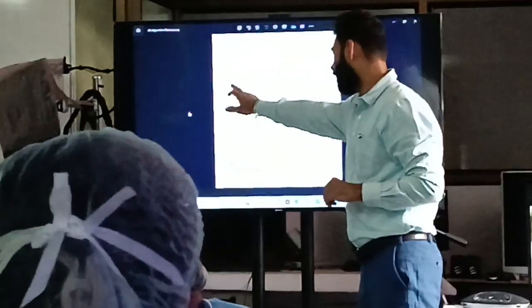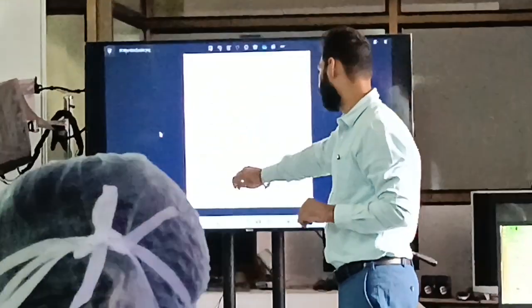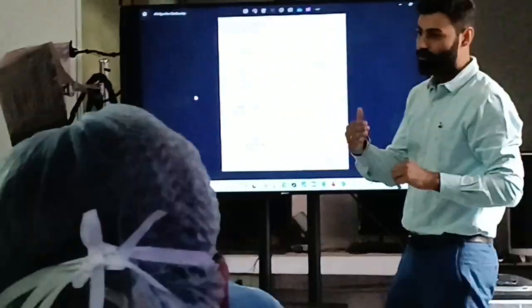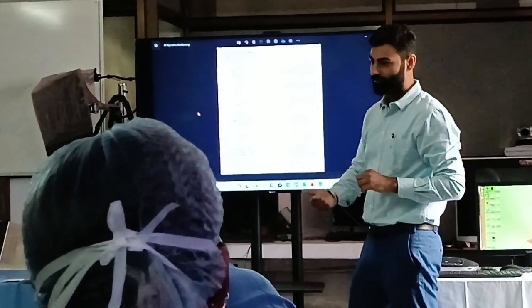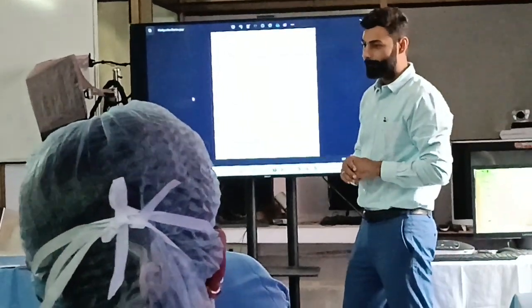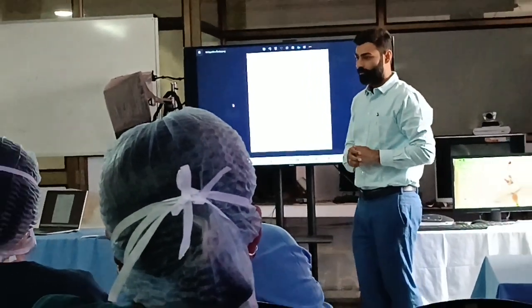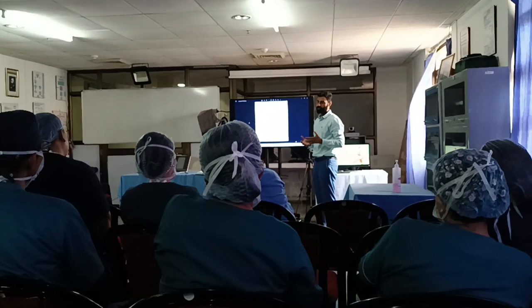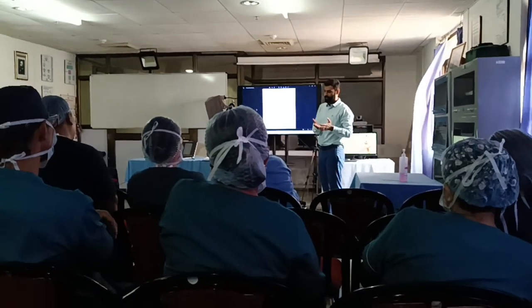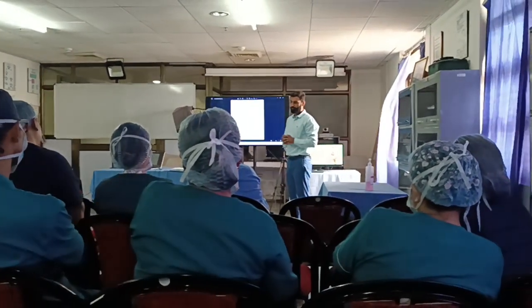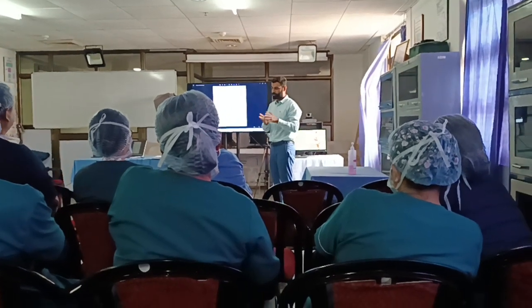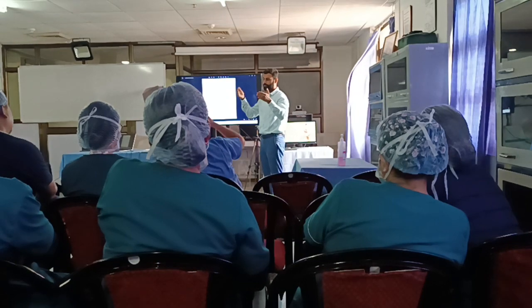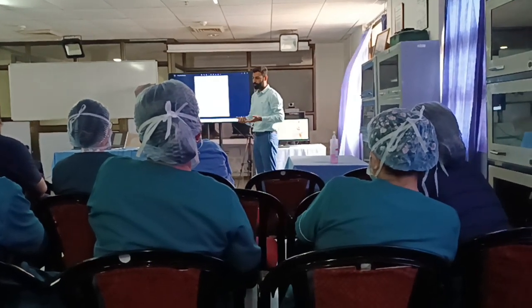If the CT of INTEM and HEPTEM ratio is more than 1.25, that means we have to transfuse with protamine. The moment you start using it, you have to run them simultaneously. Because if we know a patient is on heparin, to check the reversal of heparin, we have to do the INTEM and HEPTEM test. And if we are checking for hyperfibrinolysis, it's EXTEM and APTEM. The main tests are EXTEM and INTEM because we are checking for both the pathways.